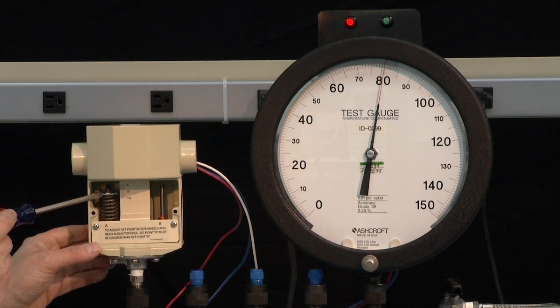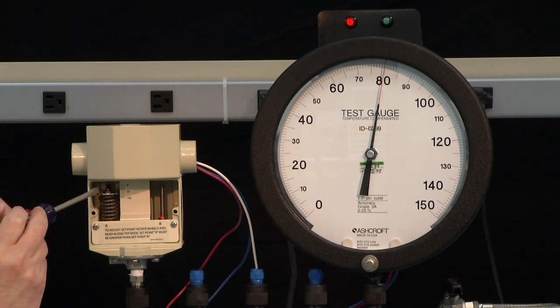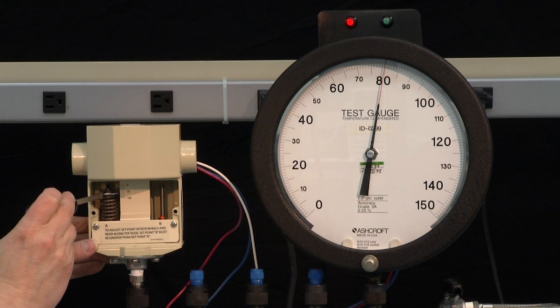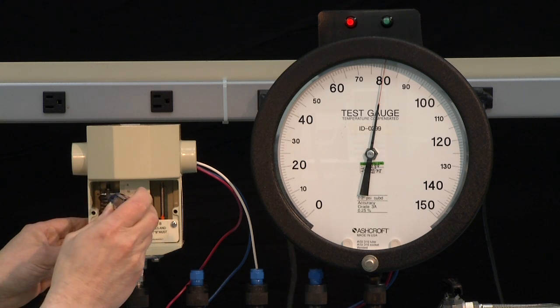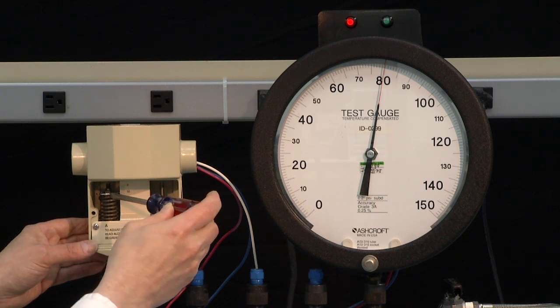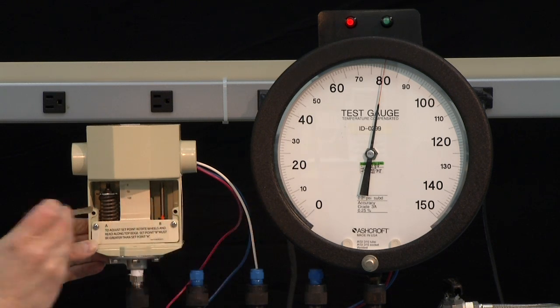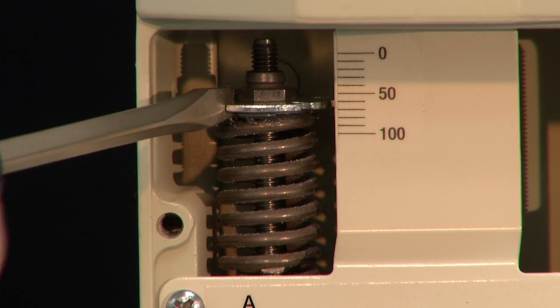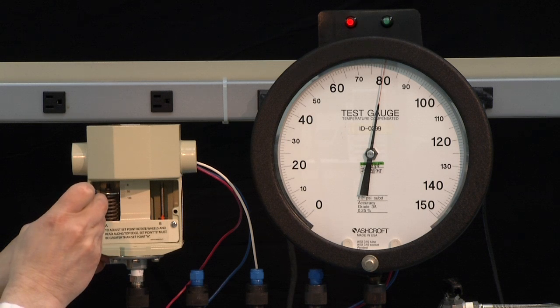Now the switch just reset. So that means my set point is above the desired set point of 80, and I am going to turn back counter-clockwise until the switch turns on. Going slowly until it just turns on.